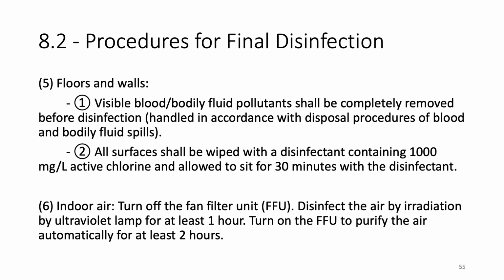6. Indoor air: turn off the fan filter unit. Disinfect the air by radiation by ultraviolet lamp for at least 1 hour. Turn on the fan filter unit to purify the air automatically for at least 2 hours.